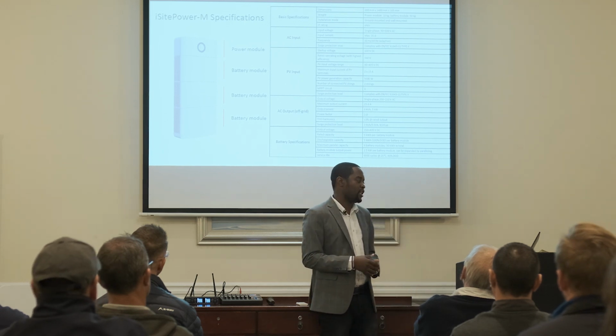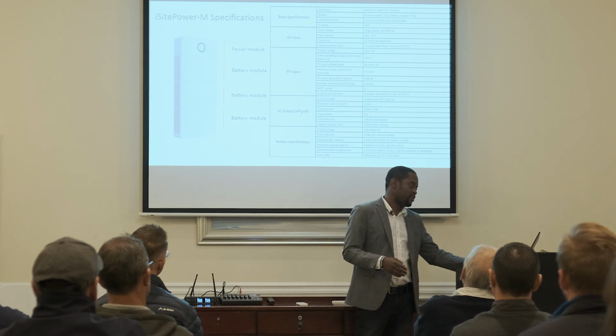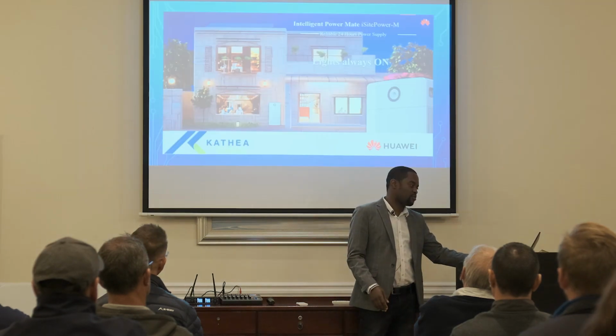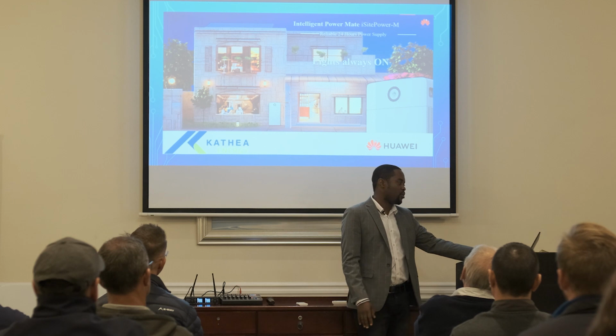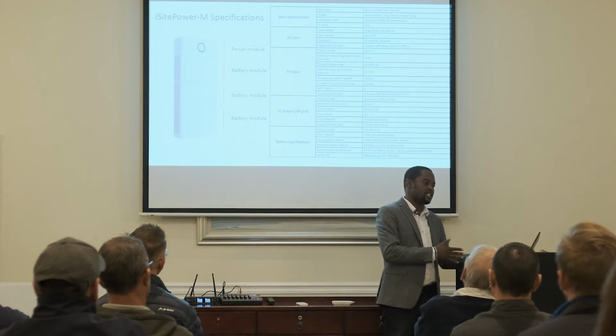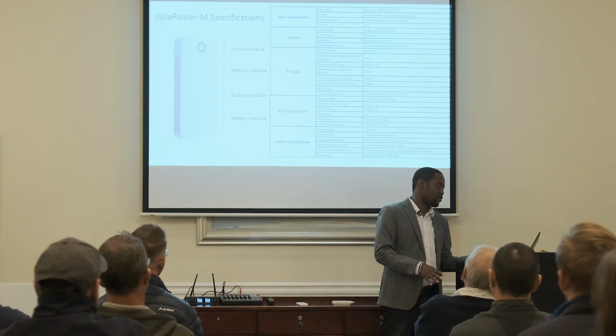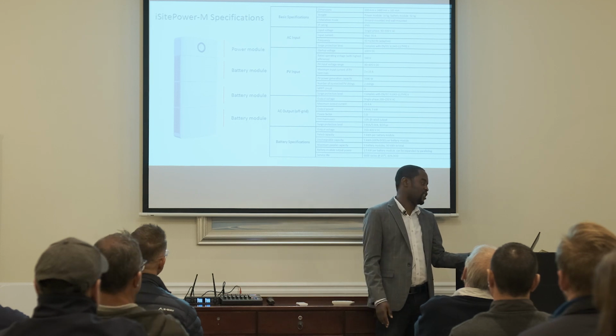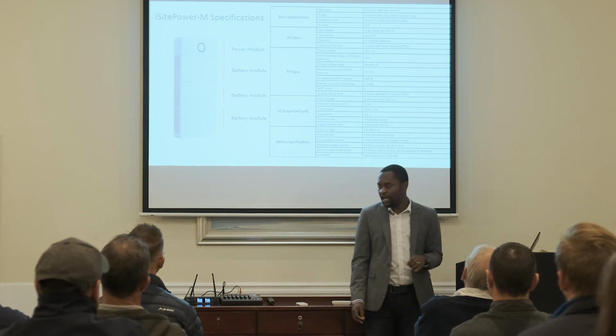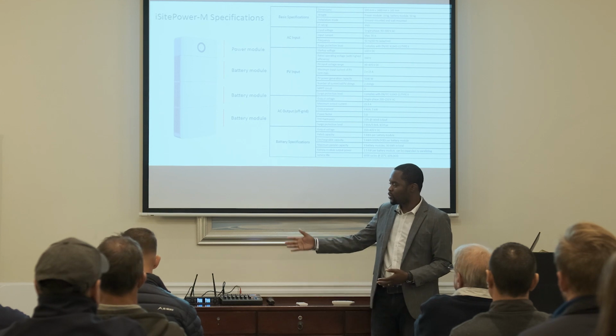You can't feed back to grid, you need to stress that, and you can't feed back to your non-essential loads. But if you size it properly and split your board and say these loads are non-essential loads, then they will never benefit from PV, but whatever is on the output will benefit from PV. So it comes stackable. The top part is the inverter.